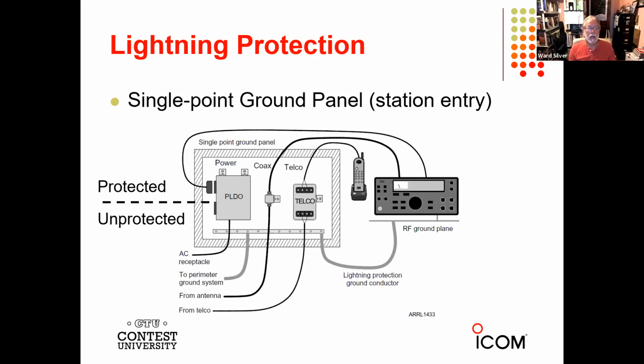And then that panel is heavily grounded with a heavy conductor to your perimeter ground system. And then from the panel, you run your protected cables, your power, your coax, your telephone, your feed lines, all this stuff, and lightning protection ground conductor. Those all go into your station. Keep the protected stuff away from the unprotected stuff.